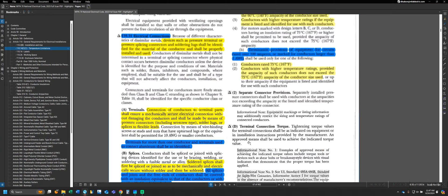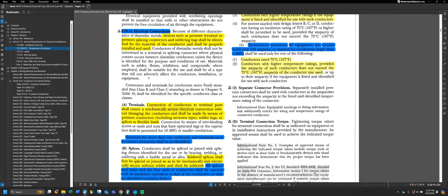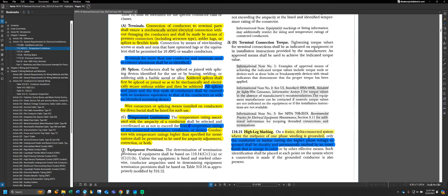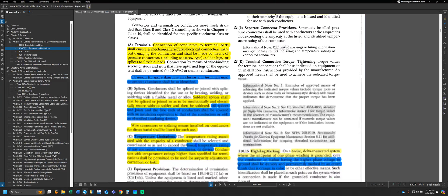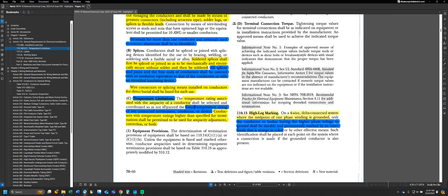The sections we're going to be looking at are 110.14(C)(1)(A) and (B). We're starting with 110.14(C) here, which lays out the groundwork of what we're going to be talking about. Part C tells us that the temperature rating associated with the ampacity of a conductor shall be selected and coordinated so as not to exceed the lowest temperature rating of any connected termination, conductor, or device.